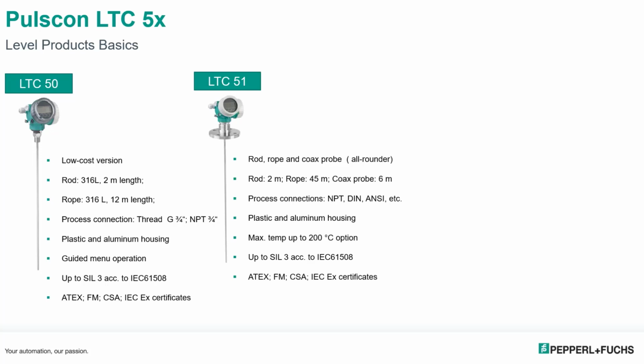The LTC51 is a little bit more, you get a little bit more options. You can get the rope up to 45 meters, and then you can get a coax up to 6 meters. The coax would be used for tanks that are cement and you can't guide your radar signal back. So the coax would be your best bet. Process connections, you can get NPT, DIN, ANSI, G-threads, and so on. Unlike the LTC50, the LTC51's flanges are available. 200C max operating temperature option, and again, SIL 3 as well as the HAZLOC certifications.